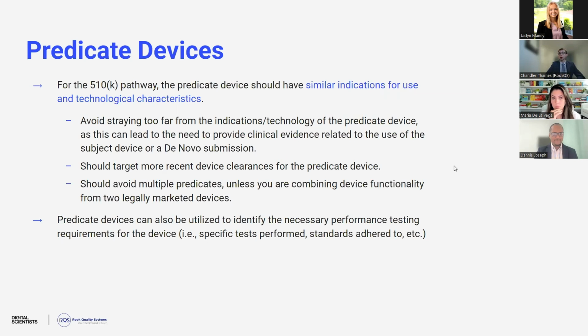So most of the time you want to have a single predicate device. There are some situations where having multiple predicates may be appropriate. So if you're combining device functionality from two legally marketed devices, similar technology, in those instances, you can have a second predicate, but this is something that you need to make sure is absolutely necessary because FDA really does like to see that single predicate.